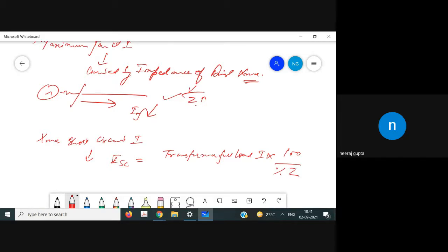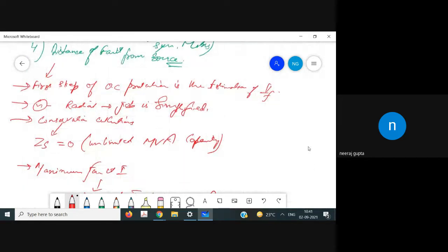While calculating the short circuit current, a common practice is to lump all the motors that are connected together, treating them as if they are on a common bus. Assuming a group of motors with transient reactance of 25%, the typical contribution is 4 times the full load current. So this is about what the fault current is and what it depends on.